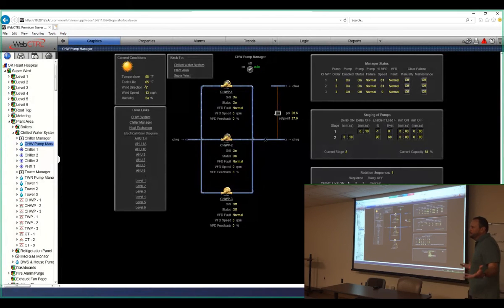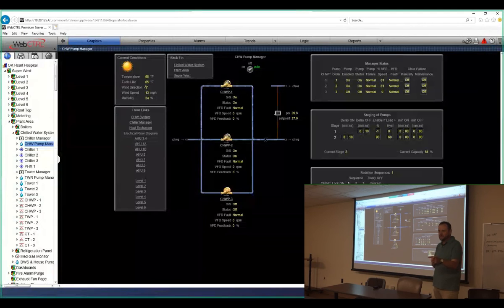So really we give you multiple options. Maybe you want to do it based on runtime, maybe you want to do it monthly, weekly, daily. Different people have different theories. Some want to do it every day at 9 a.m. so they're on site, and want to make sure somebody's there, that way when it rotates, we have somebody there and can just pop in and check it. That's some people's theory. Other people's theory is, in facilities where the plant turns off, I don't want it to rotate till 2 o'clock in the morning. Rotate the pumps while we're off, that way when it starts back up, I've got a separate pump start. And so that's the reason you've got the different options.